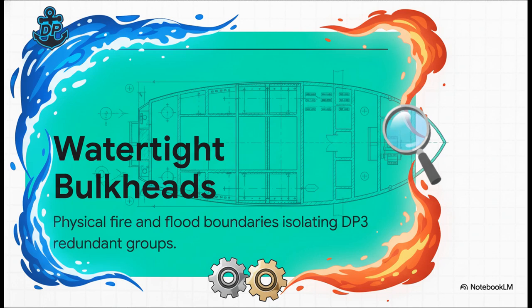Now, to confirm that design intent holds up in reality, we follow a strict procedure to confirm the integrity of the A60 fire and watertight bulkheads between the engine rooms. We rigorously test these because physical separation is literally the only thing guaranteeing that a localized fire or a sudden flood won't wipe out both your main and redundant equipment groups at the exact same time.